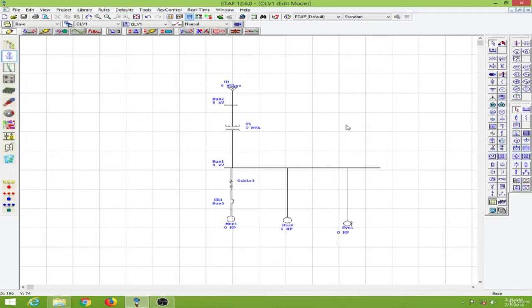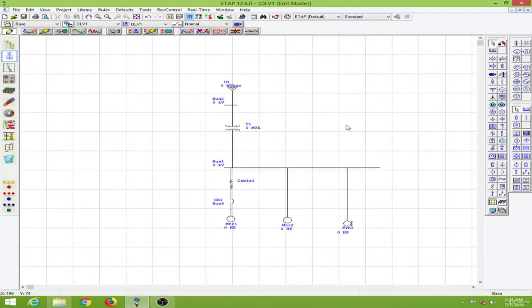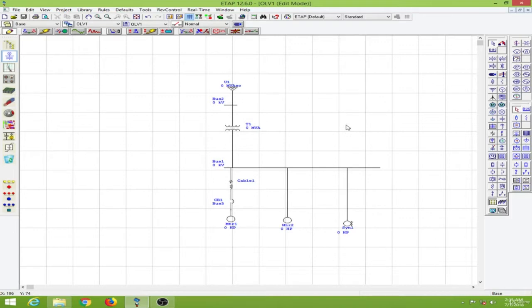In case of AC induction motors we see that it works as a rotating transformer. So at rest what we have is the short circuited secondary. So what happens is that due to the short circuited secondary there will be a large inrush current in AC induction motors. However this current reduces depending upon the slip value. When the slip starts to reduce the short circuited secondary conditions slowly start to diminish and become settled over time.